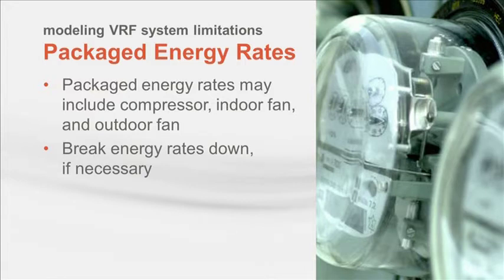Oftentimes, we'll see users model a packaged energy rate which contains heat rejection fan power and then model a separate heat rejection component. In essence, the condenser fan power is being accounted for twice. Some simulation programs have the ability to automatically break the energy rates out based upon user-specified indoor and outdoor fan power. Check with your software vendor to see which components are simulated and how. From there, you should be able to determine which component energies should be entered into the simulation.